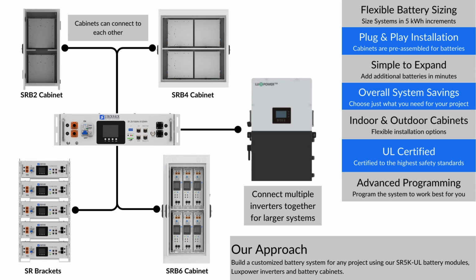The ability to choose which cabinet you need for which project and the number of batteries lets you help reduce overall system costs. All of our battery cabinets, except for the SR brackets, are outdoor rated. And then I'll talk about this in just a few minutes. I have some dedicated slides for this, but some really advanced programming that you can do with the Luxpower inverters for time of use, for peak shaving, self-consumption, etc.